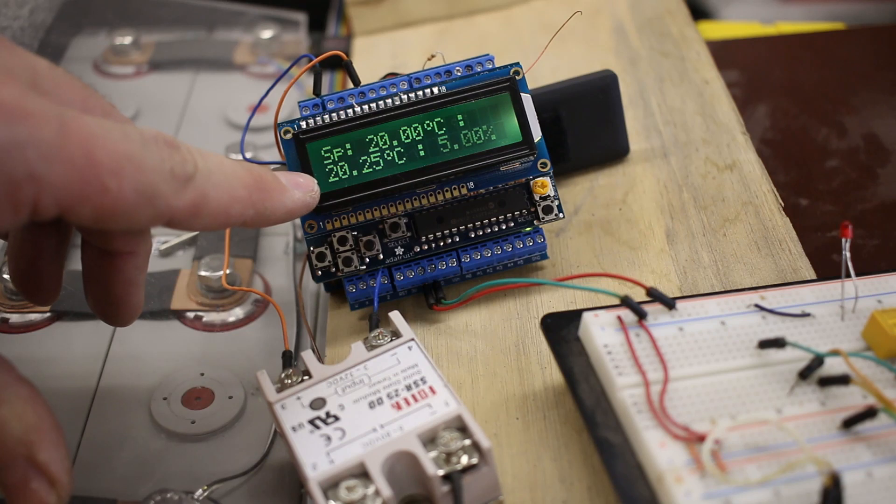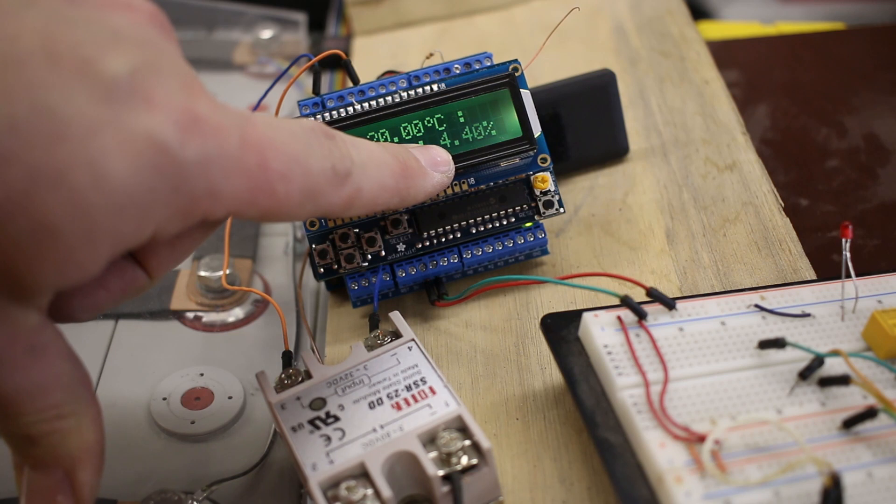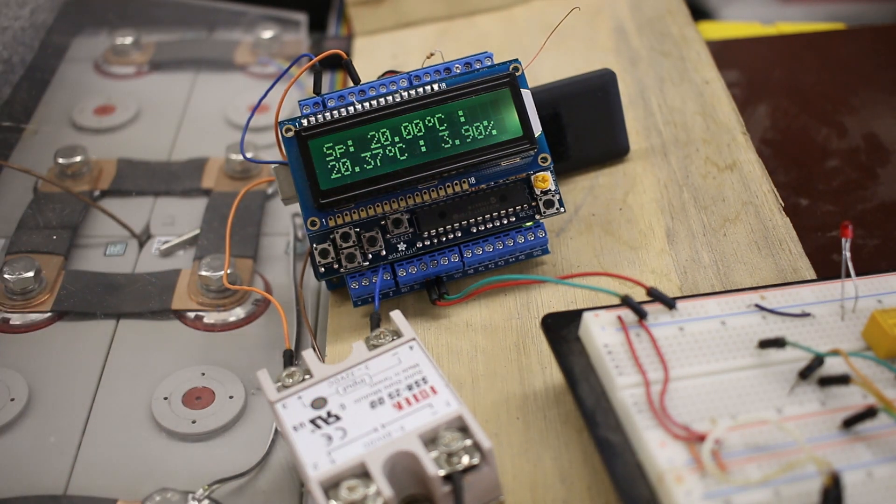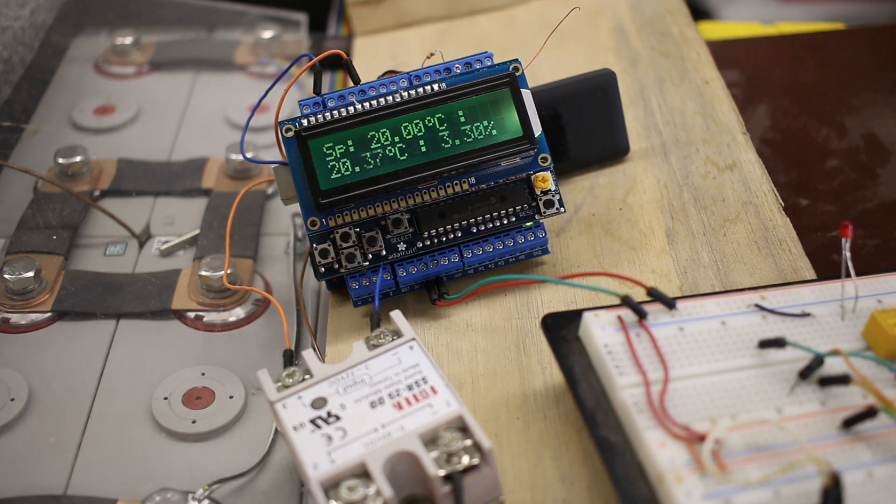And you can see the percentage of the time, the percentage of the 10 seconds that the relay clicks in is down to four percent and it just keeps dropping here, see that. So as it gets closer, the amount of time the relay goes on reduces so that it doesn't overshoot. It prevents that thermostat issue where it overshoots and then undershoots, just up and down, up and down.